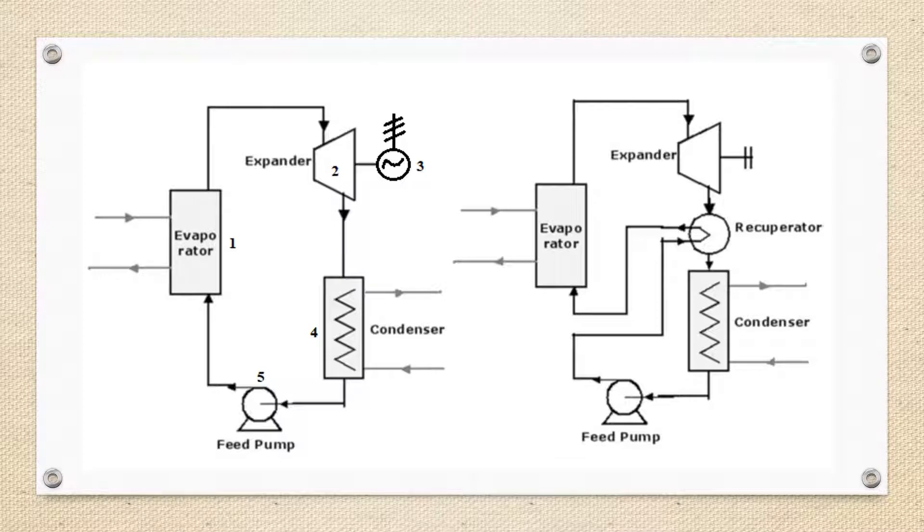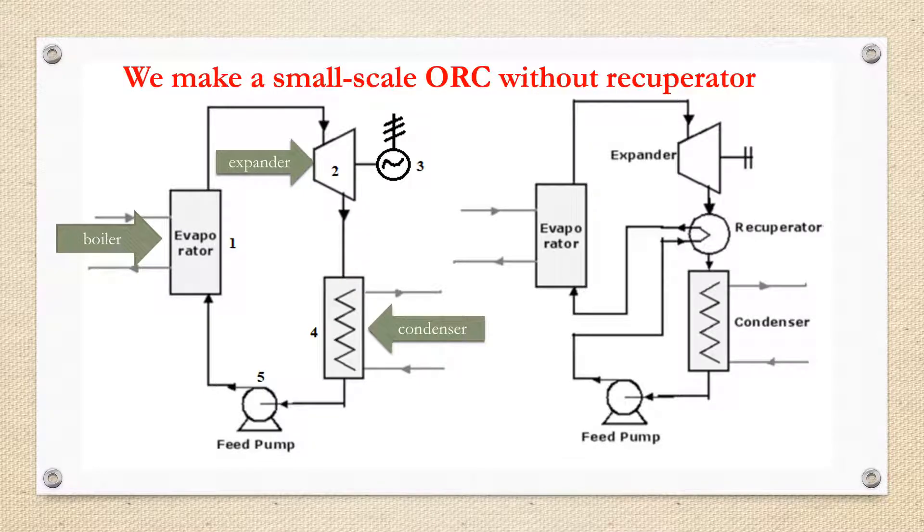The working fluid is pumped to a boiler where it is evaporated, passed through an expansion device (turbine or other expanders), and then through a condenser heat exchanger where it is finally re-condensed. We make a small scale ORC without a recuperator, so the basic cycle is very similar to the traditional steam cycle.